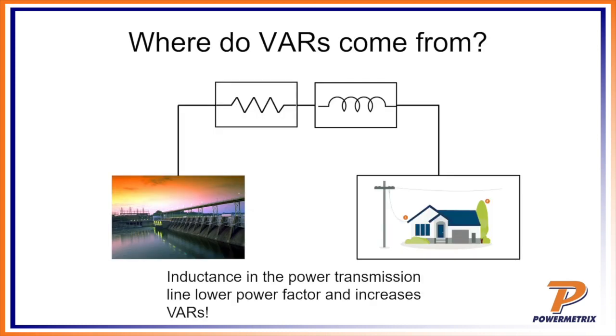So where do VARs come from? Most of them come from the inductance on the power line coming down to the customer. The customer can also worsen their power factor based on their load, and therefore it can cause more positive VARs in that situation.